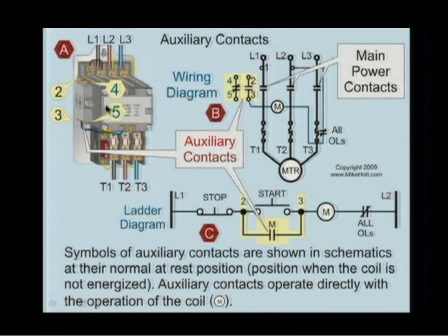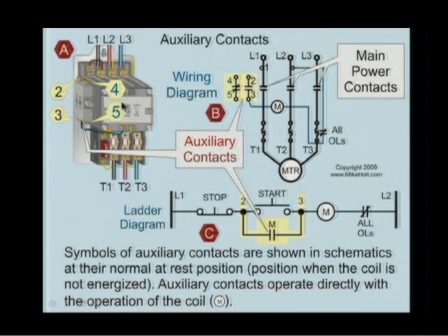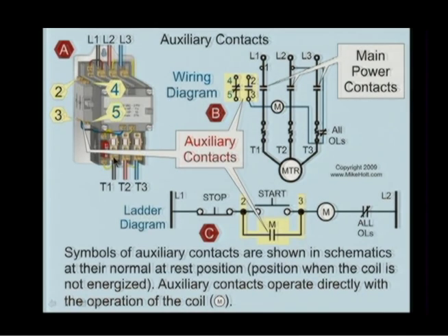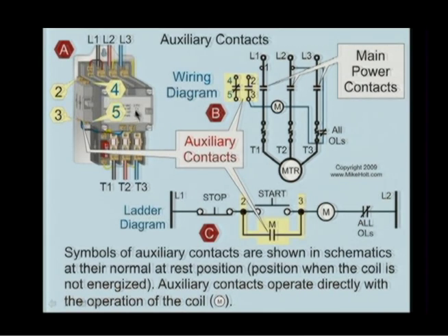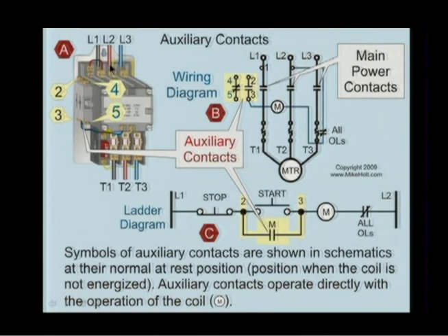Inside this motor starter, there are three main contacts. This is essentially a switch that we're going to close. When we close this switch, the three main contacts take power from line one and present it to terminal one, line two to terminal two, and line three to terminal three. There's a coil here that draws in the contacts using an electromagnetic field. When that closes, there are contacts that are auxiliary — in addition to the main contacts — and that is your auxiliary set of contacts.